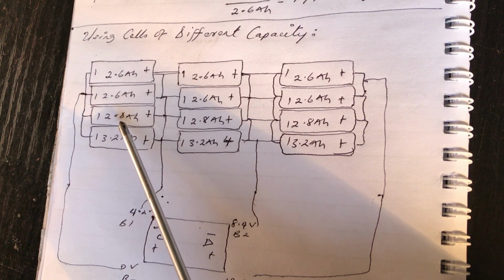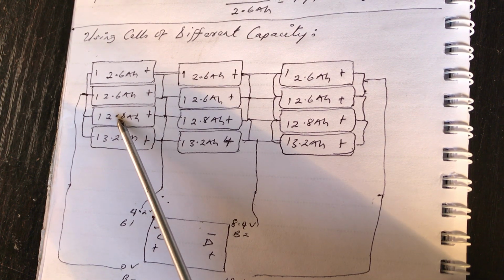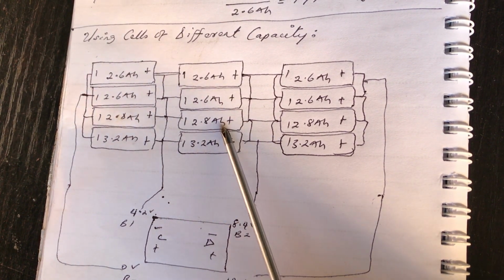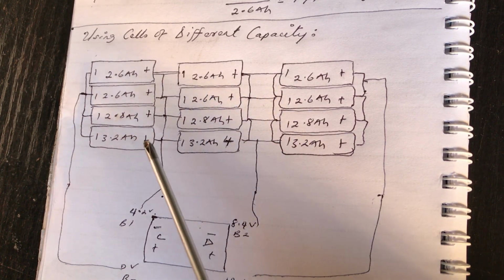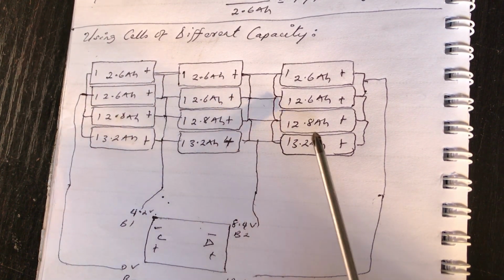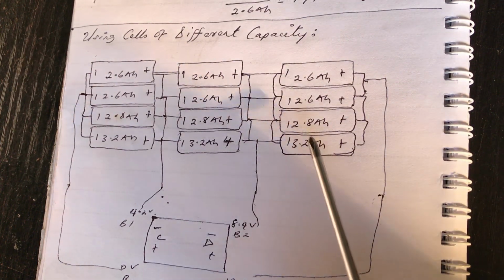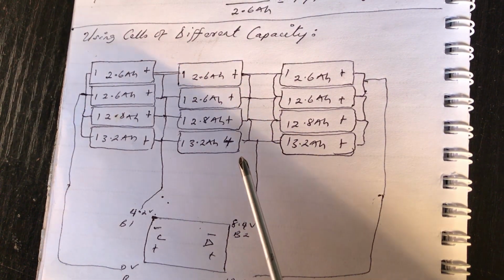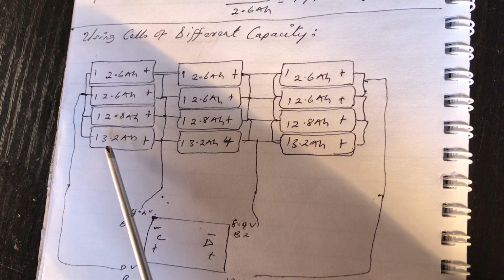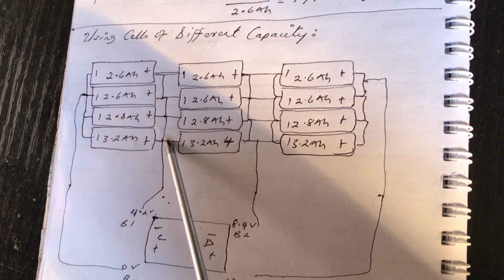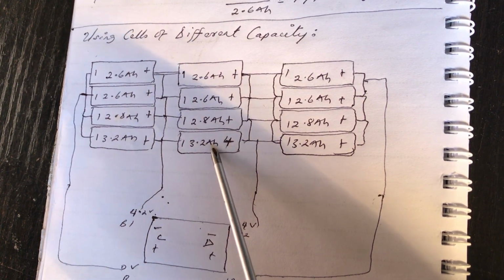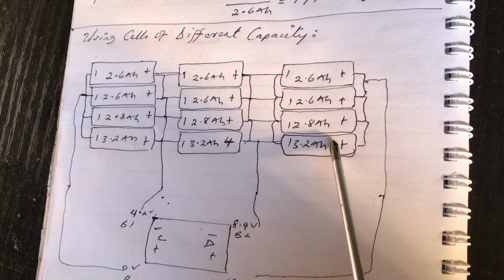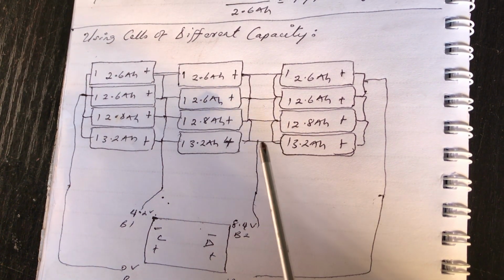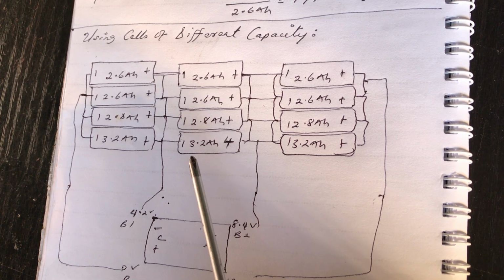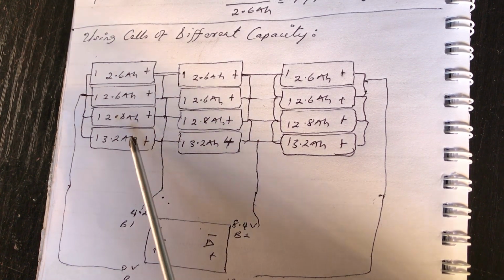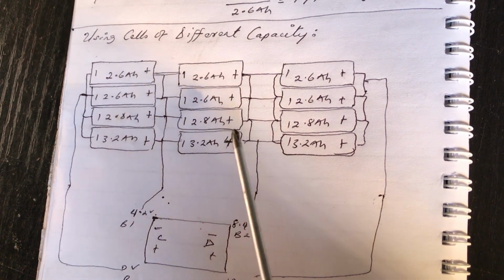On the third line of the battery arrangement, you've got 2.8 ampere hours, 2.8 ampere hours, 2.8 ampere hours, then 3.2, 3.2, and 3.2. If you continue to stack up your cells this way under each cell pack, making sure that what you have on a given line for cell pack 1 matches cell pack 2 and cell pack 3, you can ensure some level of balancing of voltage and capacity across the entire battery bank.